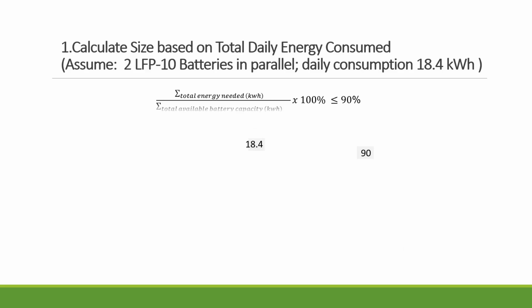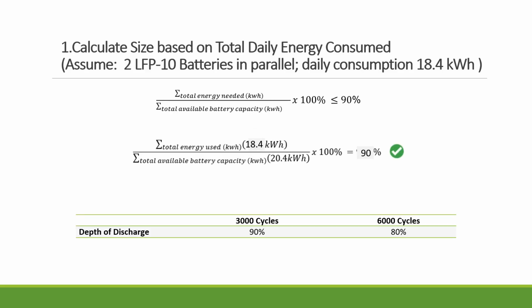The first thing is based on the total energy consumed. In this case, it is 18.4 kilowatt hour. Now you want to make sure of the depth of discharge. You don't want to fully discharge the battery, because if you do that, it will shorten the lifespan. We guarantee 90% at 3,000 cycles and 80% at 6,000 cycles.